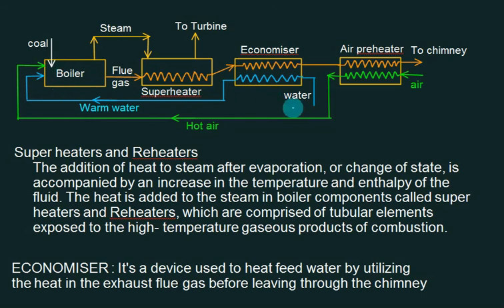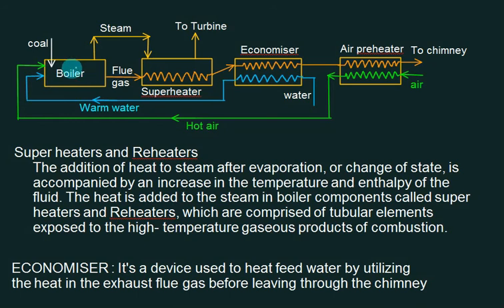From the water side, we have normal pressurized water from a pump, which is supplied through the economizer. Flue gases at high temperature pass through, so indirect heat is transferred to the water, raising its temperature — some heat recovery takes place. If the water temperature at the inlet to the boiler increases, naturally the latent heat of vaporization will also decrease, and thereby a certain amount of heat is recovered in the economizer.